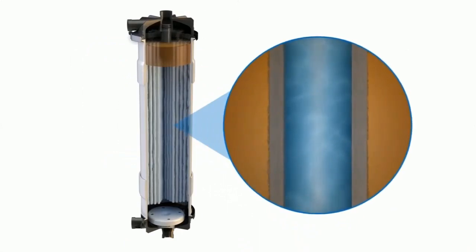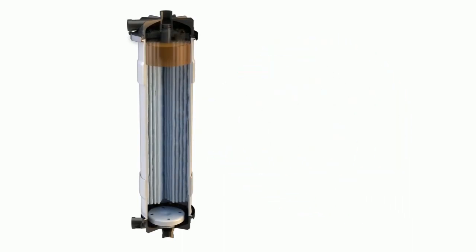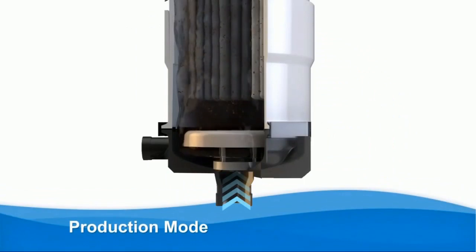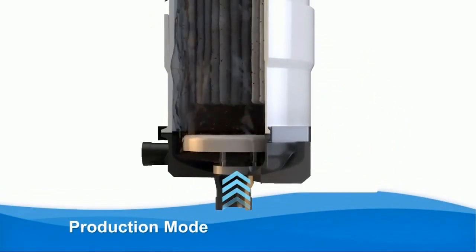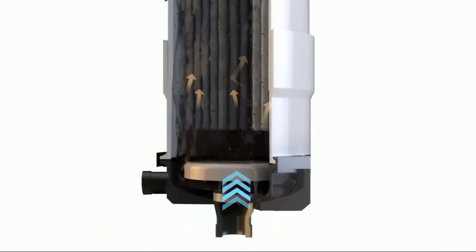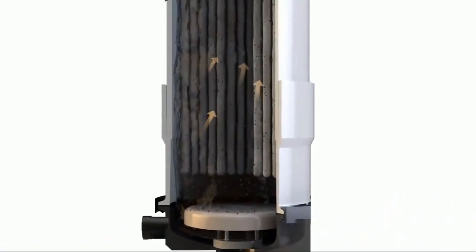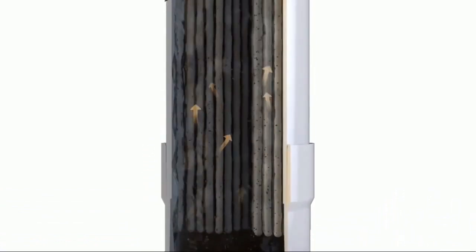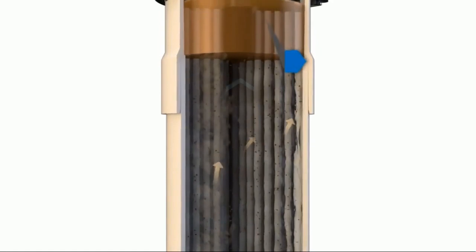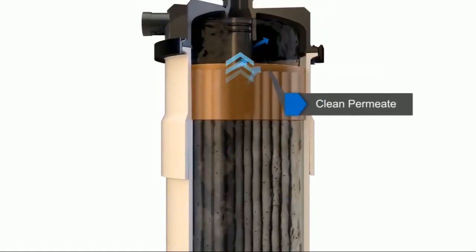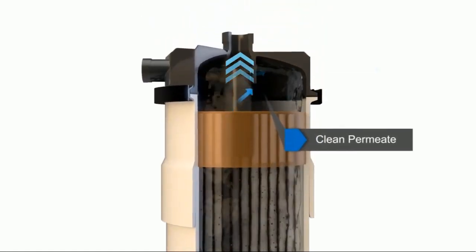The Deaphos filtration system operates in dead-end mode with outside to inside flow pattern. In production mode, feed water enters from the bottom of the cartridge and flows under pressure through the length of the pipe. Clean permeate simultaneously exits the top of the cartridge with solids concentrated within the housing. This unique approach allows for high system feed water recovery.